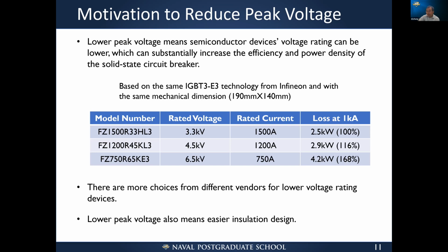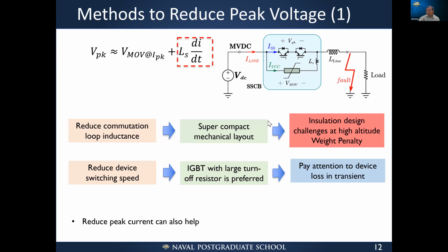And by the way, we have to meet the insulation requirements at high altitude, and none of the devices is designed for that. So we have to screen them and evaluate their performance. Also, lower peak voltages mean easier insulation design at high altitude. 6 kilovolts is much more challenging than a 3 kilovolt design. So how do we do this? How do we reduce the peak voltages?